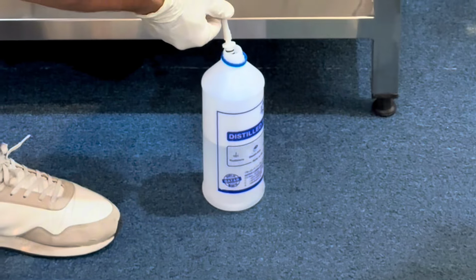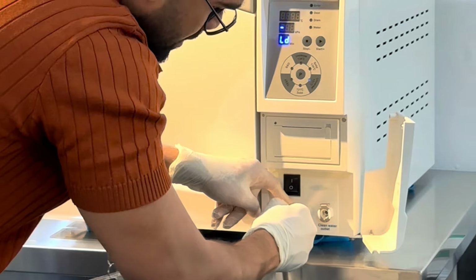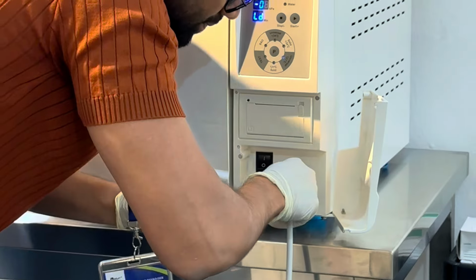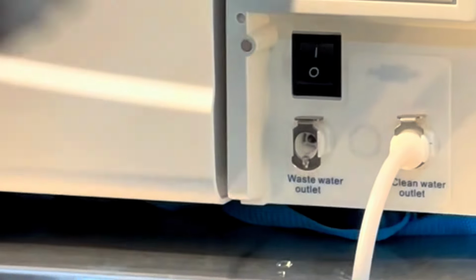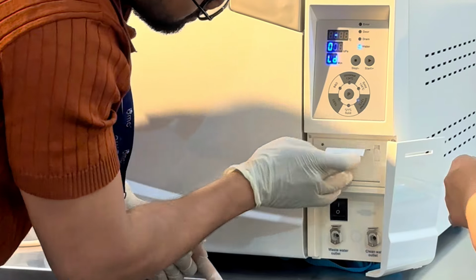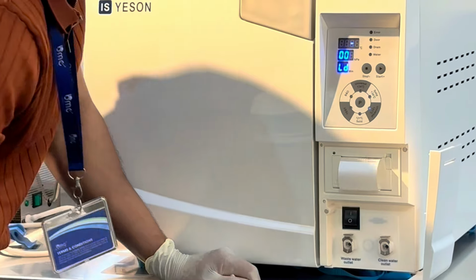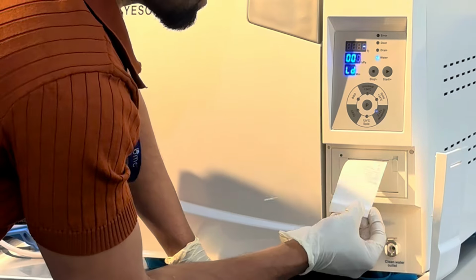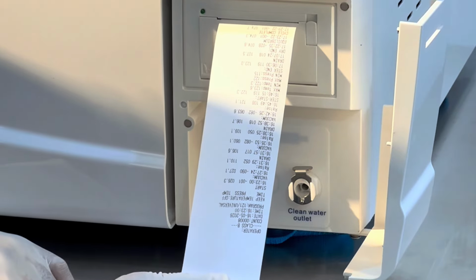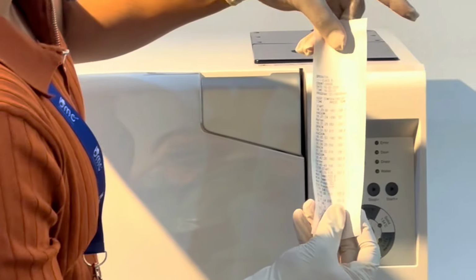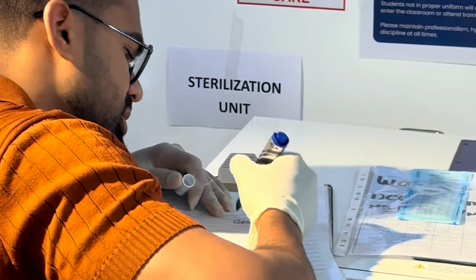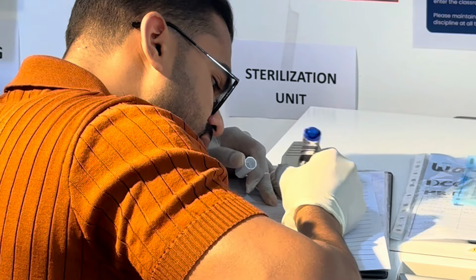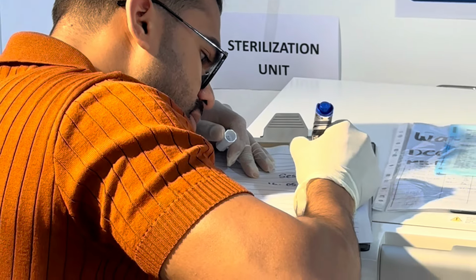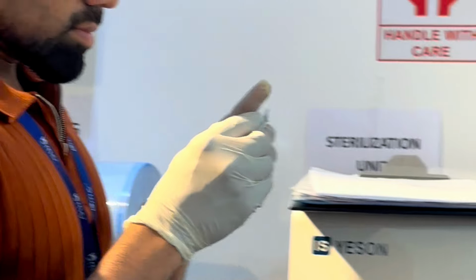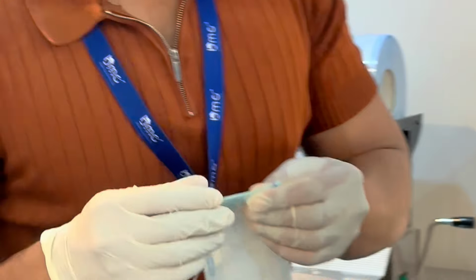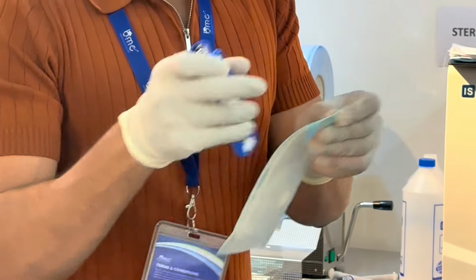Remember, sterilization is not just about cleaning instruments. It is a continuous chain of infection control designed to eliminate all risks of cross-contamination for our patients. Once the cycle concludes, the machine will generate the official sterilization report. Do not simply file this away. It is your legal and operational proof of safety. Take a moment to carefully verify the data. Check that the peak temperature, pressure levels, and total exposure time exactly match your protocol requirements. Make sure to record them carefully.